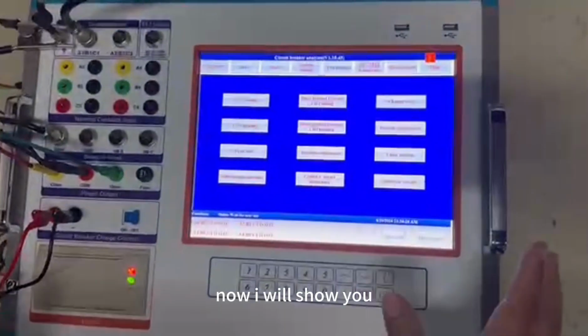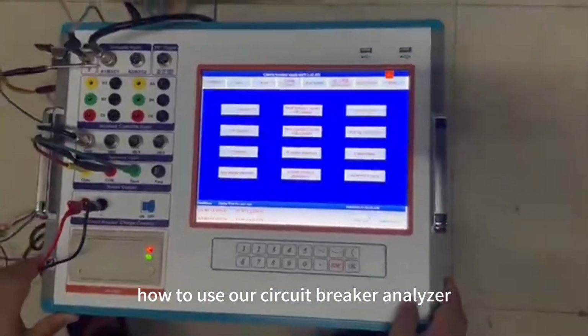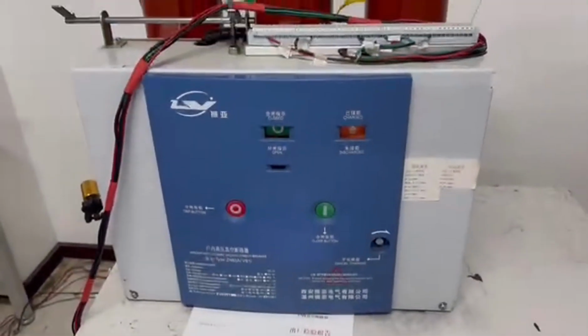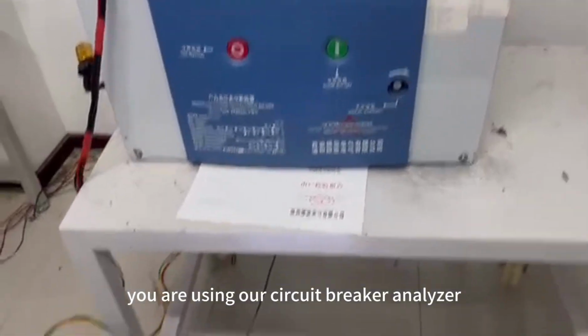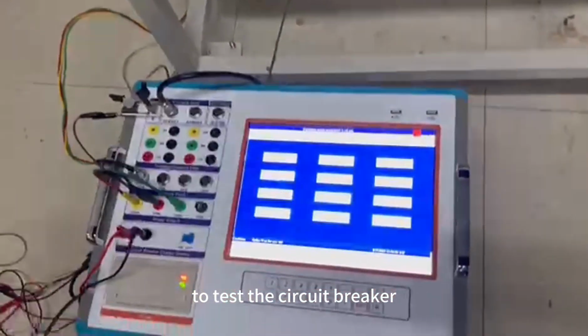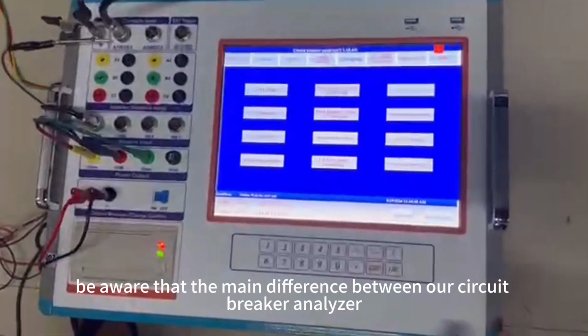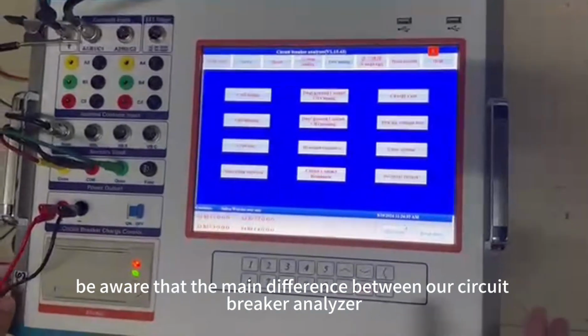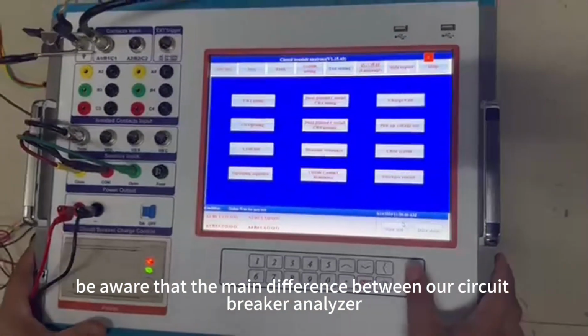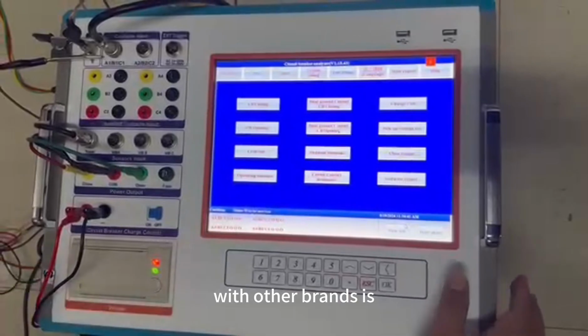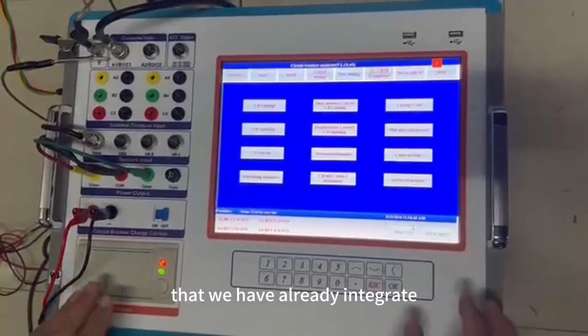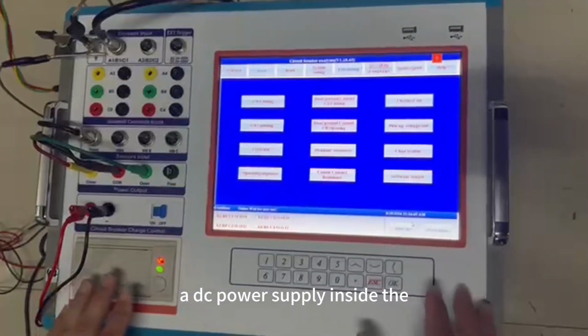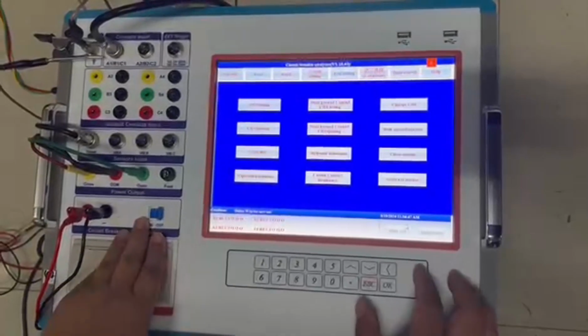Now I will show you how to use our circuit breaker analyzer to test the circuit breaker. If this is the first time you're using our circuit breaker analyzer to test the circuit breaker, please be aware that the main difference between our circuit breaker analyzer and other brands is that we have already integrated a DC power supply inside the circuit breaker analyzer.